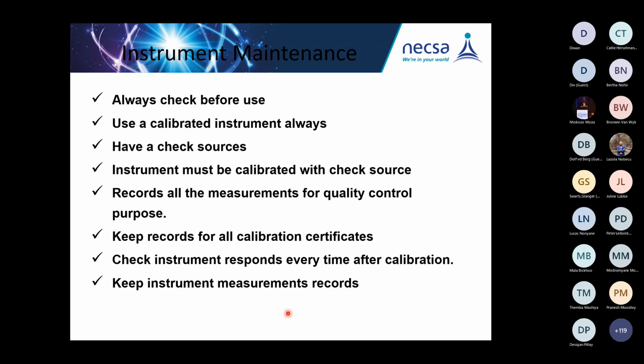Record all the measurements for quality control purposes. Every time you check the check source measurement, you can record the data and say, today it is reading this, so that you can have a trend of data, which at the end of the day tells you whether your instrument is still reliable and whether you can still trust it.